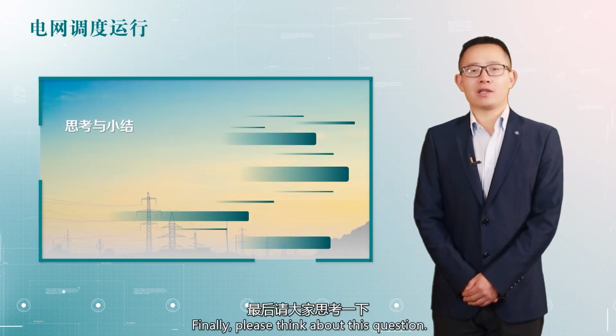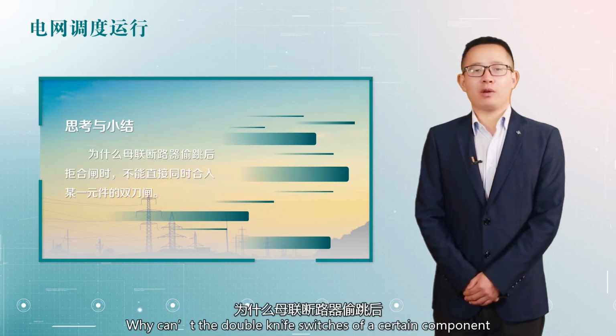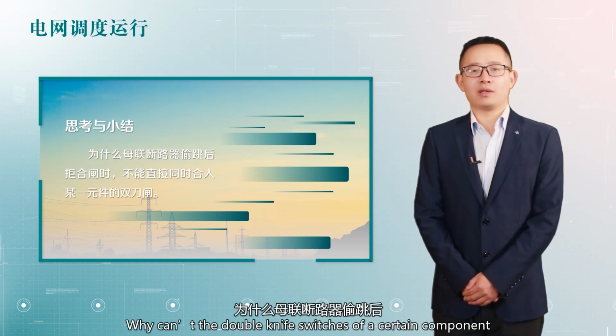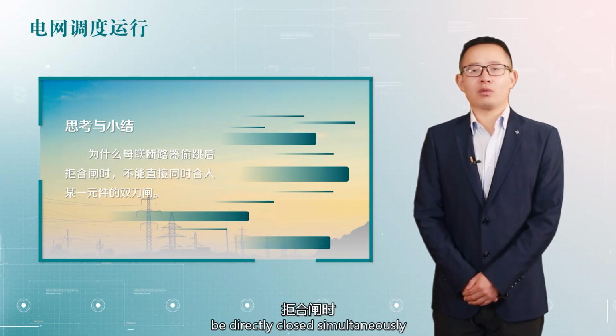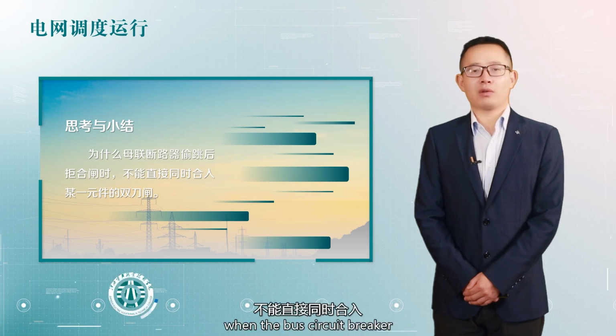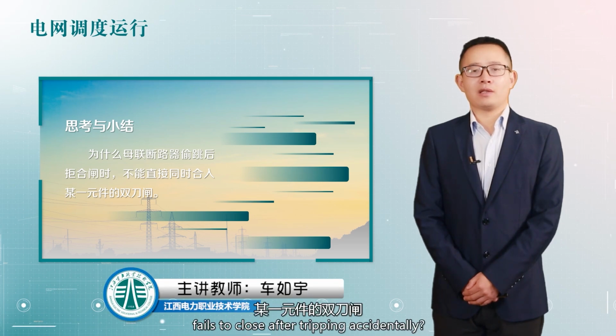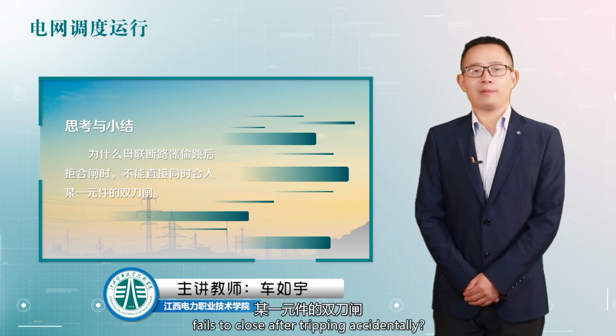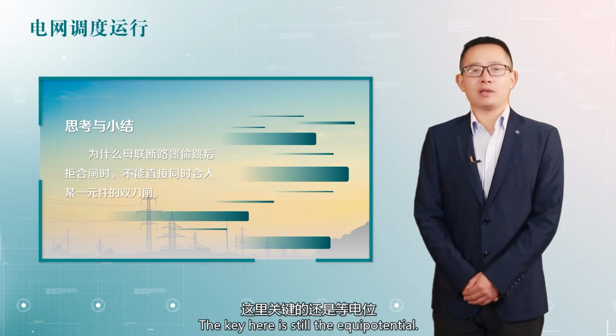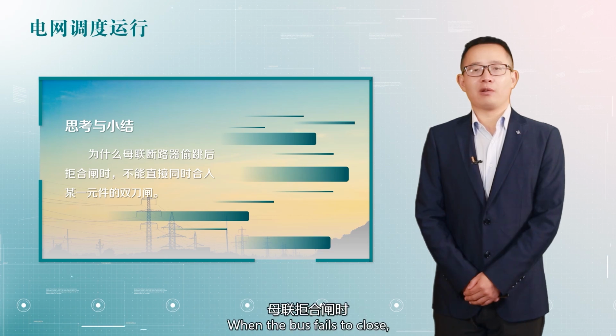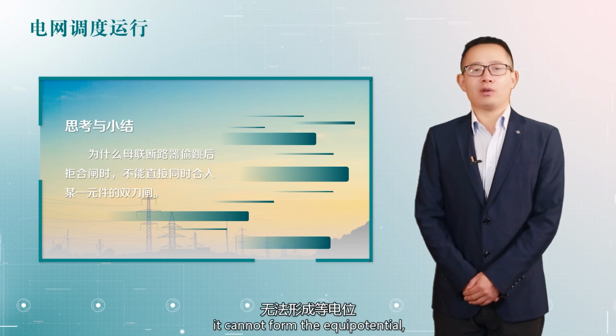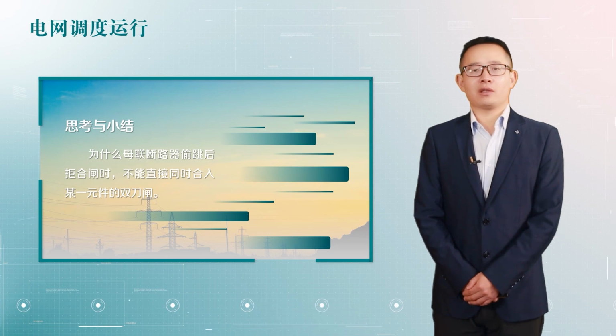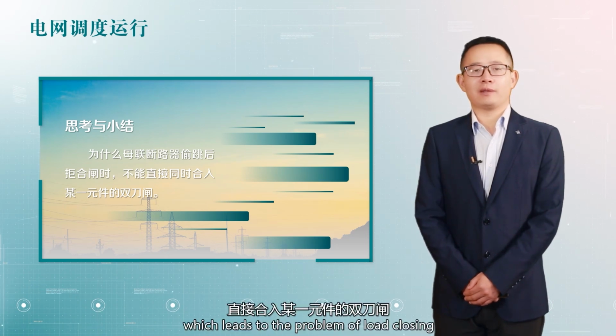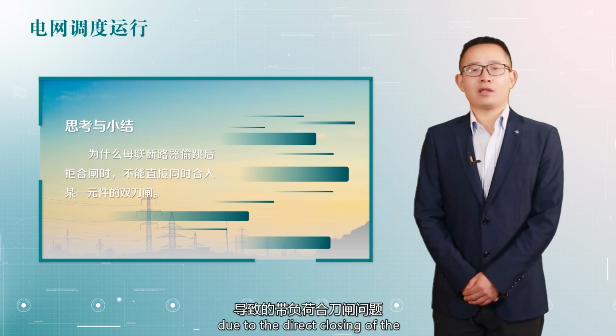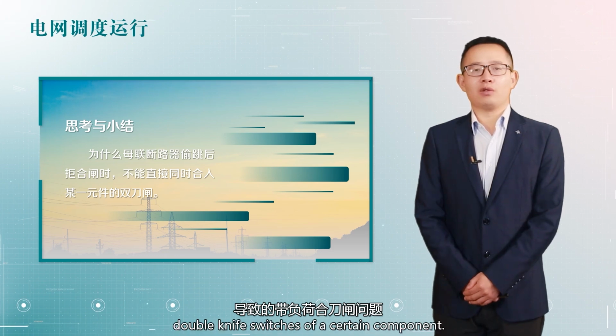Finally, please think about this question. Why can't the double knife switches of a certain component be directly closed simultaneously when the bus circuit breaker fails to close after tripping accidentally? The key here is still the equipotential. When the bus fails to close, it cannot form the equipotential, which leads to the problem of load closing, due to the direct closing of the double knife switches of a certain component.